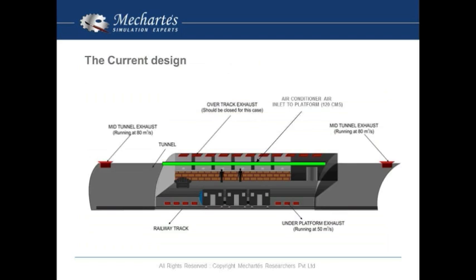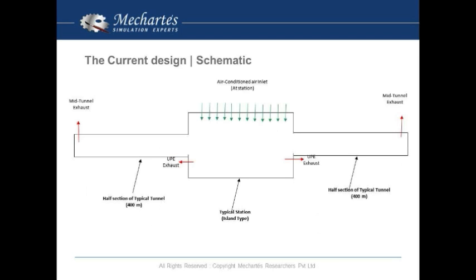The ventilation system that was existing was like this: there was a mid-tunnel exhaust running at 80 CMS, an under-platform exhaust running at 50 CMS, and an air-conditioned air supply at 120 CMS through the false ceiling and ducted supply coming from the air handling unit. This is how the schematic looked, and this was the CFD model chosen for the project.